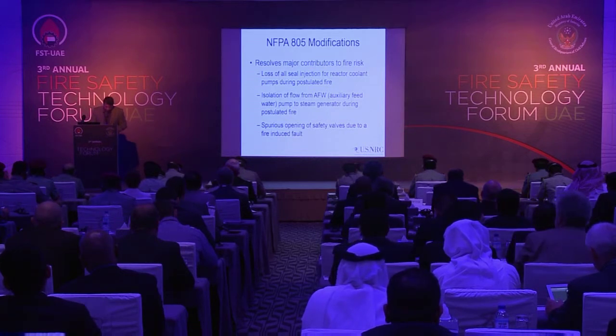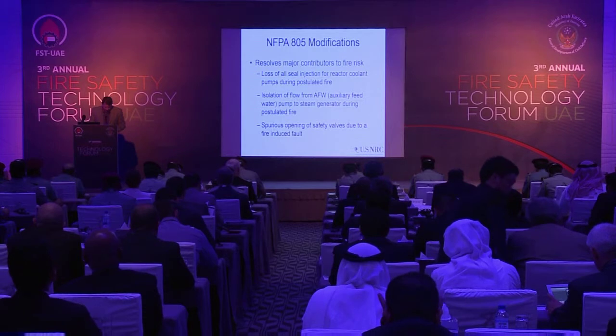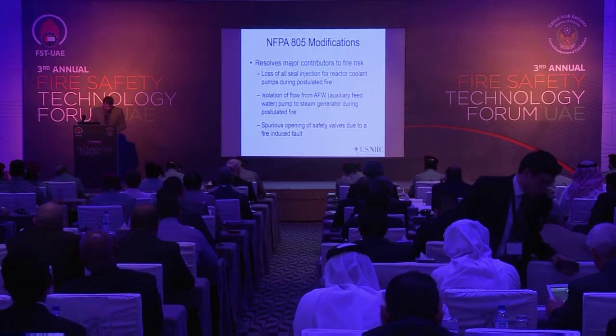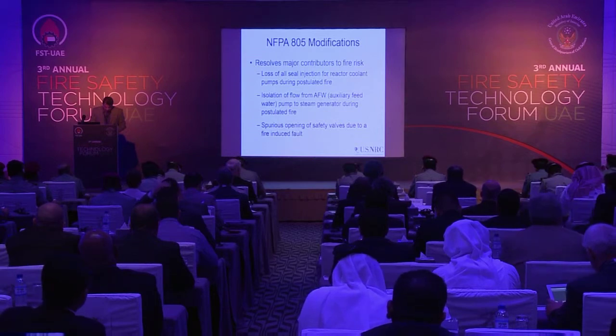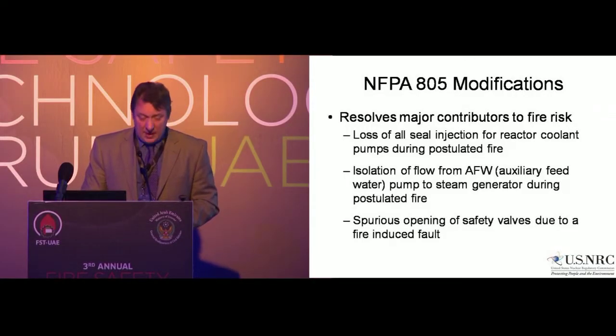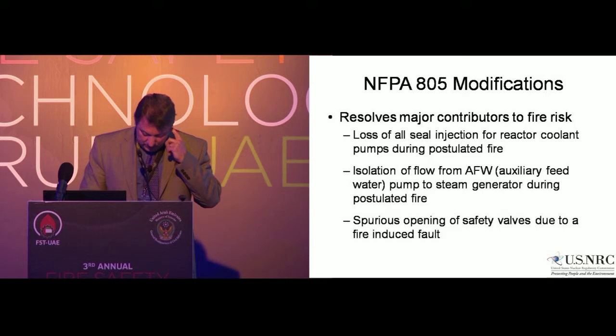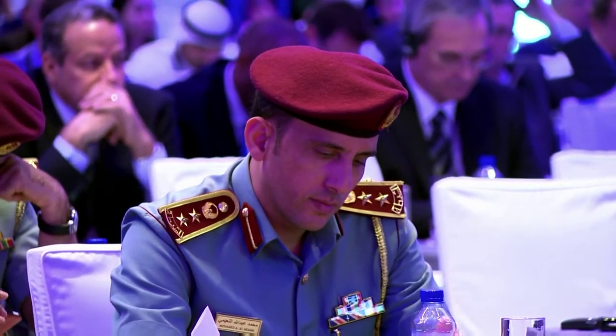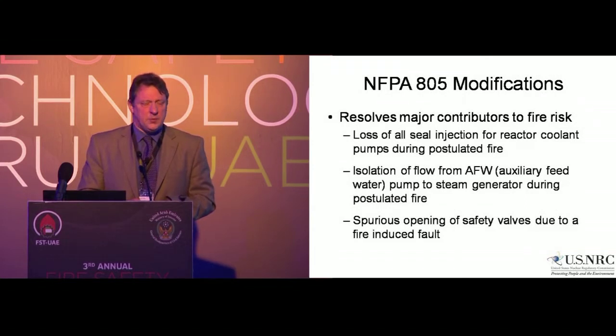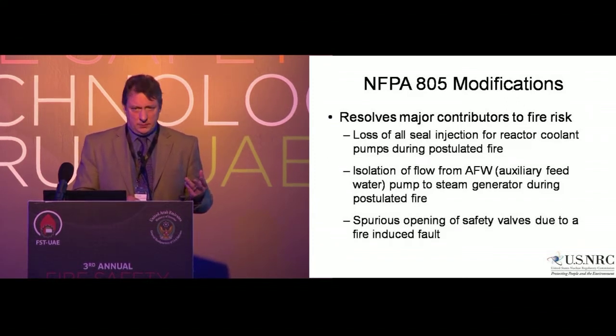In practice, plants that have gone through the NFPA 805 transition process have performed analysis that highlighted major contributors to fire risk. Based on that, they've made commitments or actually made modifications to address these major contributors to fire risk. And some of the examples, modifications, one of the biggest ones for pressurized water reactors, particularly Westinghouse plants, is loss of reactor coolant pump seal cooling. Most plants have two different means of cooling the reactor coolant pump seals, but if you do lose cooling to those seals, it can result in a loss of coolant accident.